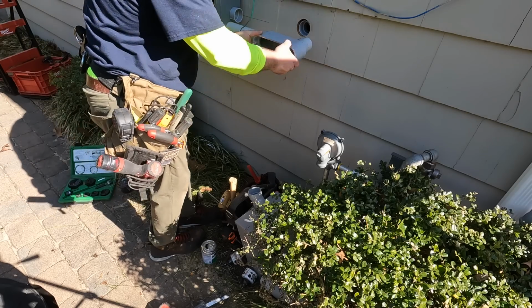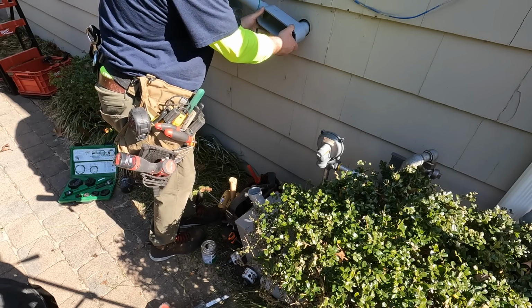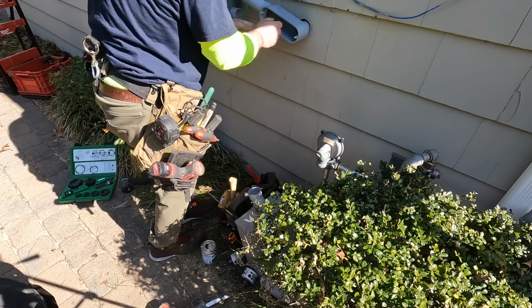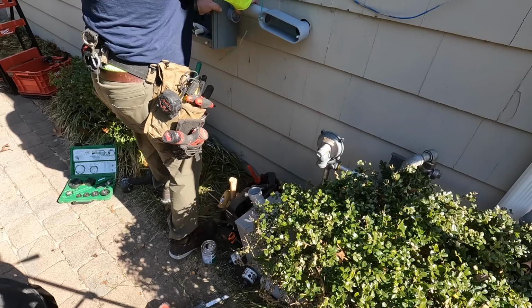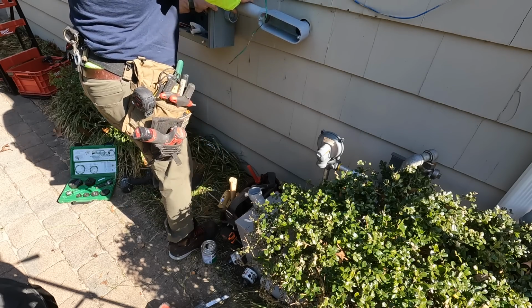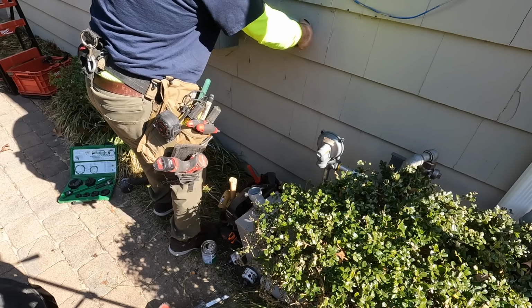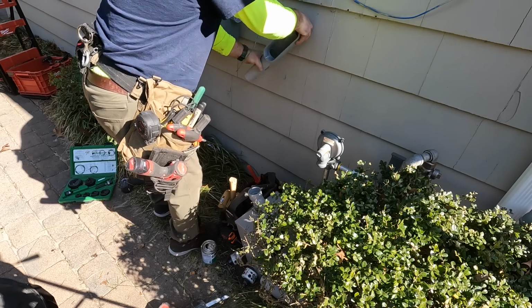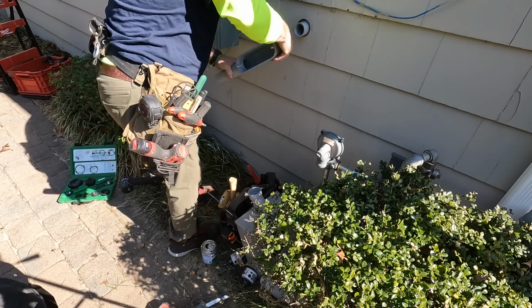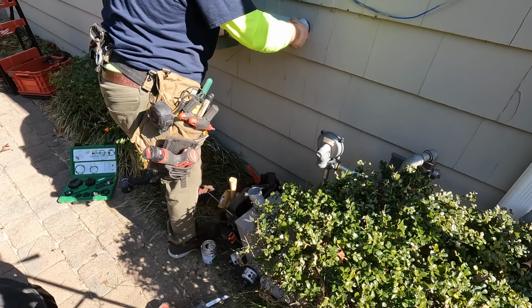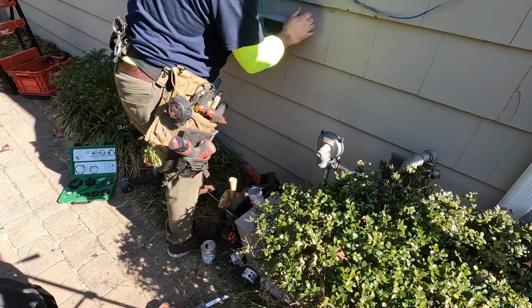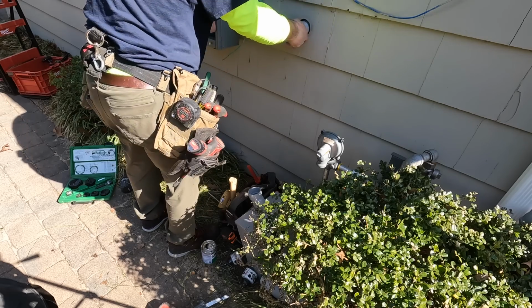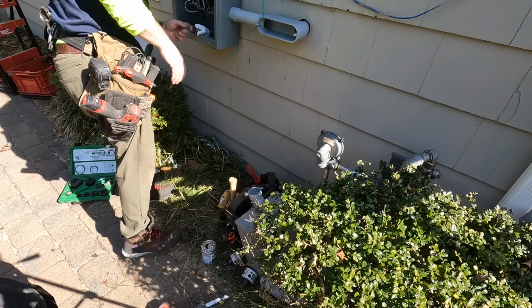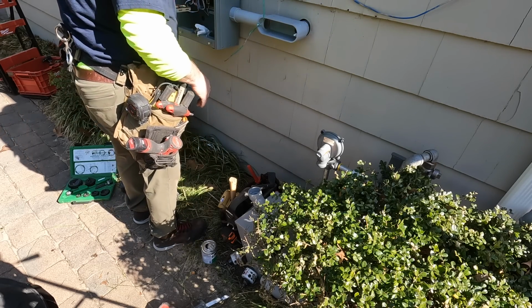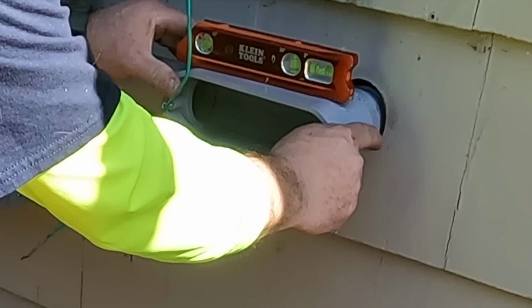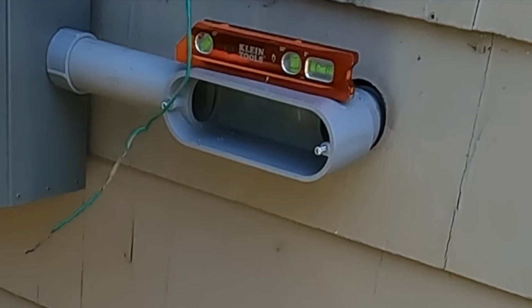What I'm doing here is extending that piece from the house side to the LB so it sits off the house evenly. I pull it back out because what I should do is put my connector side into the transfer switch first. We'll nudge the piece of conduit into the fitting and then finally into the coupling on the inside by the house there. And of course we want to make sure it's level.